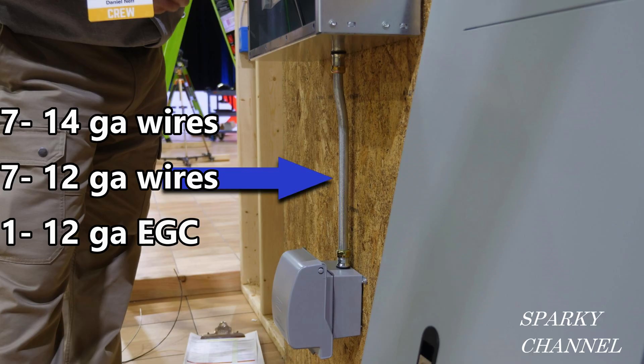So let's say you were being tested on this and there were seven 14-gauge wires, seven 12-gauge wires, and one 12-gauge EGC in the form of a green ground wire, all in this one conduit. Do you think that would be a code violation? Well, let's check it out.